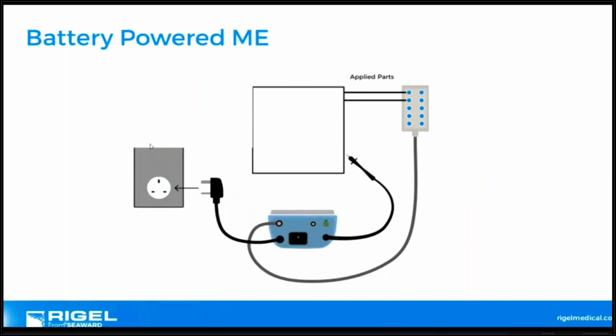Battery powered: the definition of battery powered testing is, does it have a mains connector, i.e. even a battery charger like a laptop type brick, or does it not? If it doesn't, then it's a battery powered medical device. If it has a charger or any kind of AC to DC connector, you have to treat it as if it's a class 1 or class 2 device as per 60601 or 62353.